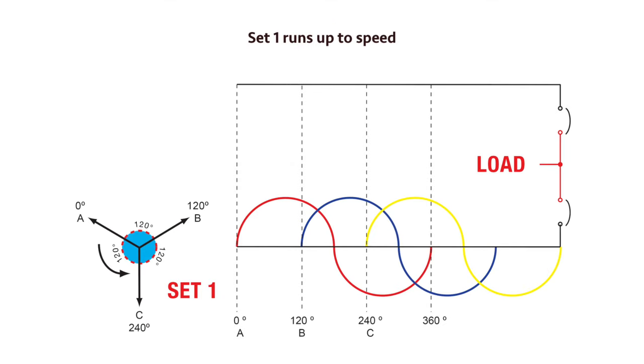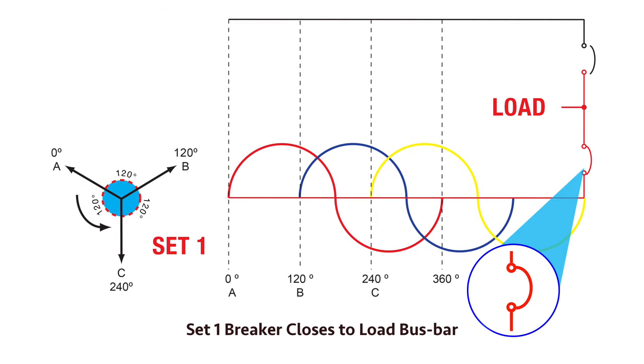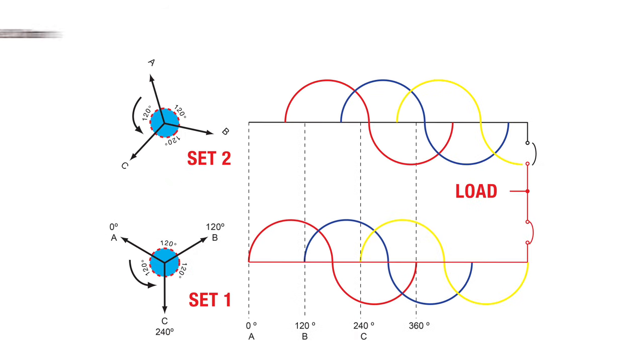Set one runs up to speed and its voltage and frequency will be the reference to synchronize with set two. After run up, set one's breaker closes to the bus. Set two runs up to speed with a breaker open.